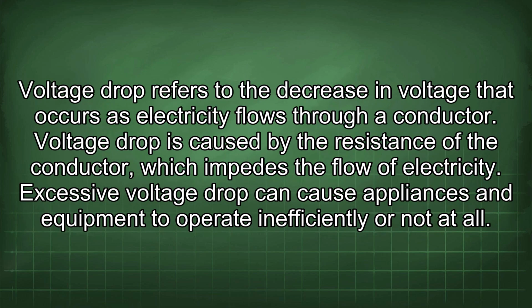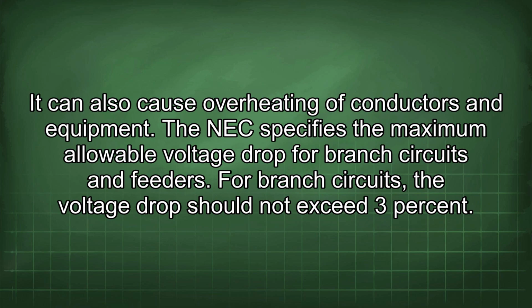Voltage drop refers to the decrease in voltage that occurs as electricity flows through a conductor. Voltage drop is caused by the resistance of the conductor, which impedes the flow of electricity. Excessive voltage drop can cause appliances and equipment to operate inefficiently or not at all. It can also cause overheating of conductors and equipment. The NEC specifies the maximum allowable voltage drop for branch circuits and feeders.